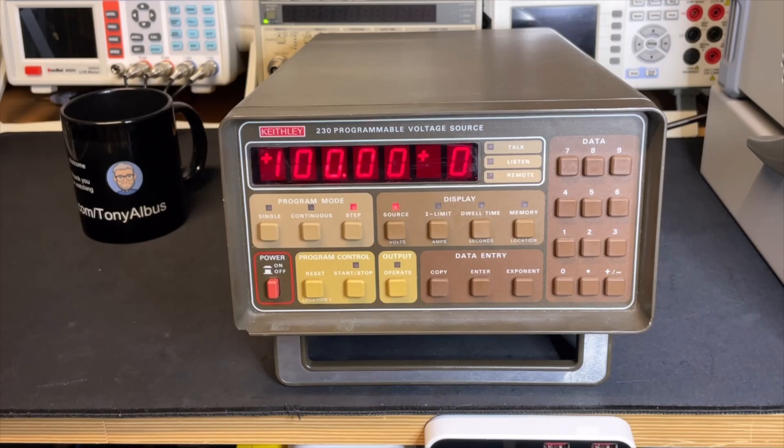And in each step, you can program what voltage you want it to output and also how fast the step is interval to the next step. And you can program that from three milliseconds up to a thousand seconds. And the time accuracy is also about 0.05%. So even the timing is very precise in this source.